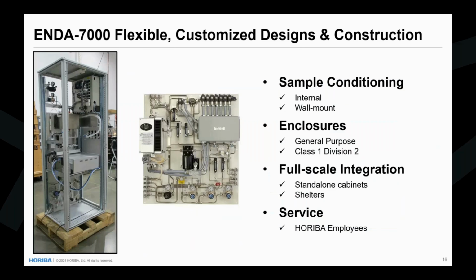All right. Successful monitoring solution includes much more than an analyzer, though. So as I mentioned before, considerations for proper sample conditioning is essential for long-term reliability of any gas analyzer system. We can install these systems inside cabinets, inside shelters. We have wall-mounted assembly solutions, which the center photograph is an example of a sample system we custom designed for one of our customers and duplicate it when that need arises for any new prospective customers. The photo at left is an ENDA-7000 cabinet that's under construction. It has its front and rear doors and its side panels removed for access, but once this system's complete, it'll be fully buttoned up, and I'll show you a photo of what that looks like from the front on the next slide.